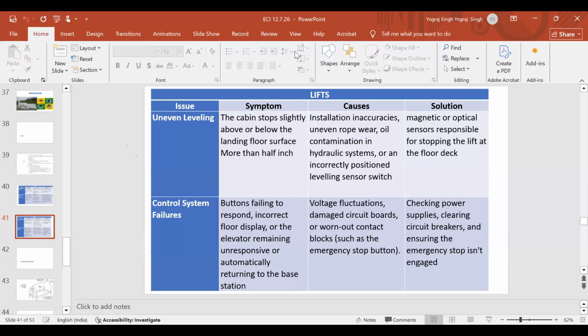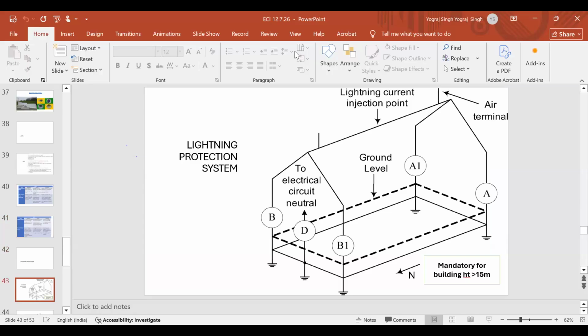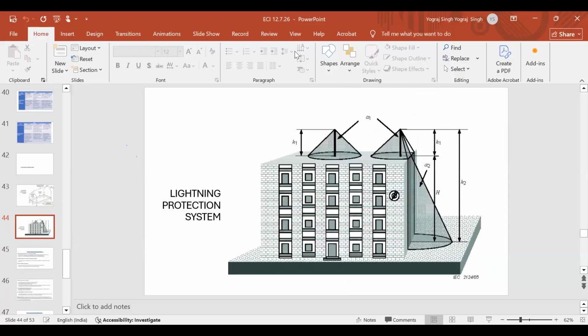Now, the next entity is your lightning protection. As you all know, lightning protections are always provided. Lightning has a tendency to come to the highest point. Now, below 15 meters, no lightning protection is needed. Why? Because the highest points will be trees. So if lightning comes from the sky, it will be caught by the trees first. So generally in a single storied building up to 3-4 storied building, lightning protection is not provided. That will be taken care of by the protection system of nearby high buildings or trees.